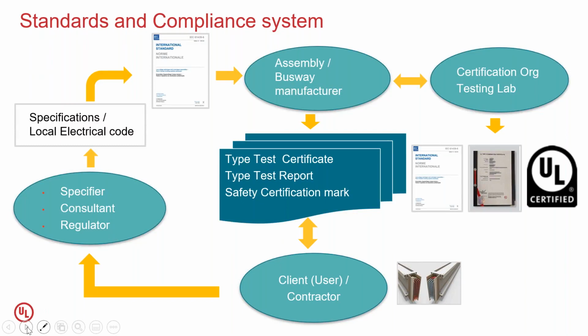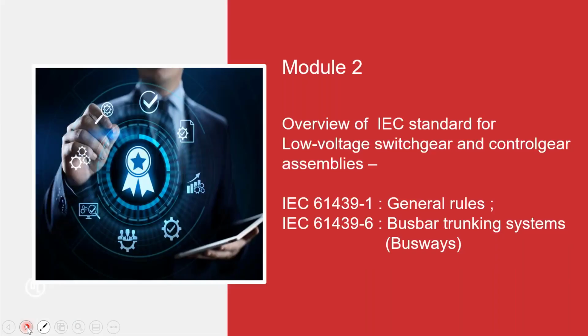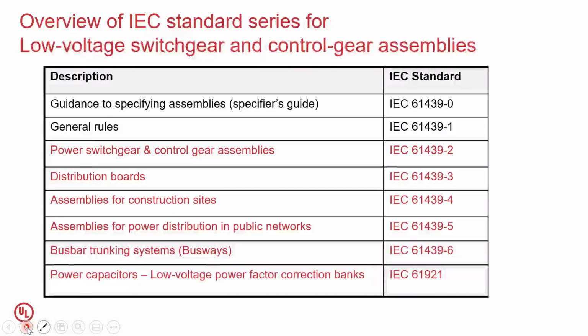Okay, so let's now move on to our second module, which is the overview of IEC standards for low voltage switchgear and control gear assemblies. We will focus on the general rules standard, and we will also talk about the busbar trunking systems. Before I go into these two standards, it is important for us to understand the series of standards that are available under the 61439. As you can see here, this is a snapshot of the 61439 series and the associated standards.